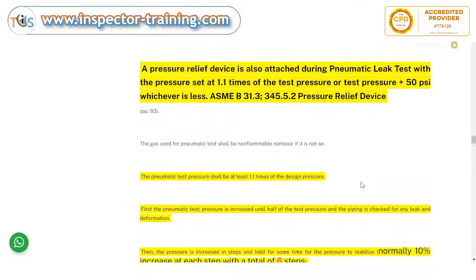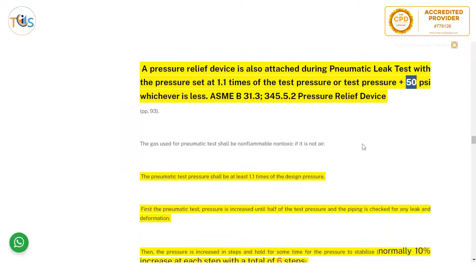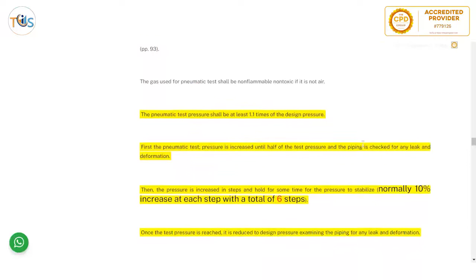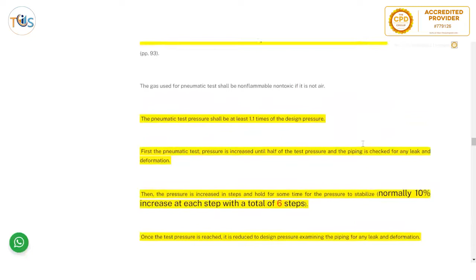That was a low pressure example. If the pressure is like 600 or 700 psi or 1000 psi, the reason they put 50 psi is that it would apply, because if it's 1000 psi, you have say 1100 psi for test pressure, and then you have 1200 psi for the relief valve. Now in this case it says 1.1 times or 50 psi, so 1200 to 1100 would be 100 psi. Because this is more than 50 psi, you use this number. So the valve should be set at 1150 psi in this case, not 1200 or 1210 psi, that is 1.1 times the test pressure.